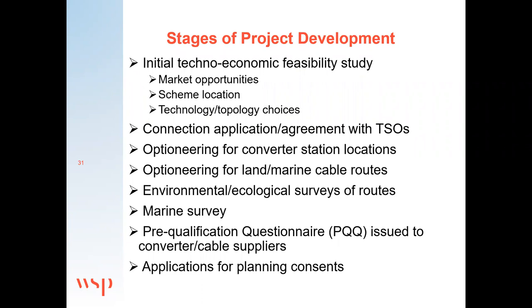The next thing to do, of course, is then go and speak to the TSOs in both countries and seek a connection application and get agreement with them that they can indeed accept, in this case, 2000 megawatts import-export power onto their network. And indeed, they have to do studies to prove that's the case. They need to do load flow studies to be sure that they can import or export the power. And they have to do some stability studies to see what happens if there's faults in their network or faults in our network. Will the system survive?